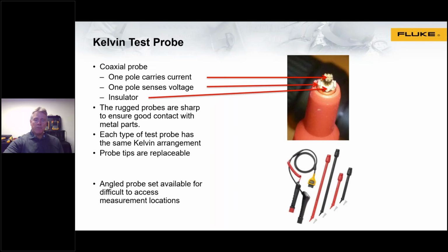The probe tips are replaceable. They're sharp. They bite into the metal you're trying to contact, so you'll have good contact. It's important that they're replaceable. That's probably a consumable item for people doing a lot of battery testing. As pictured below, we have a variety of probes, different probe lengths, and also angled probes, all with these tips, to be able to access difficult measurement locations.